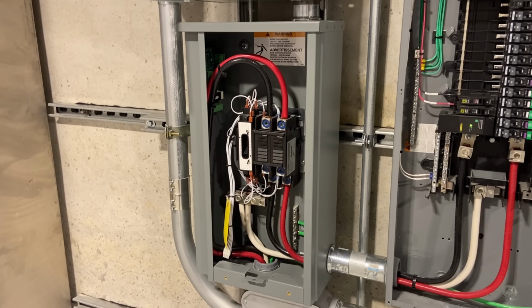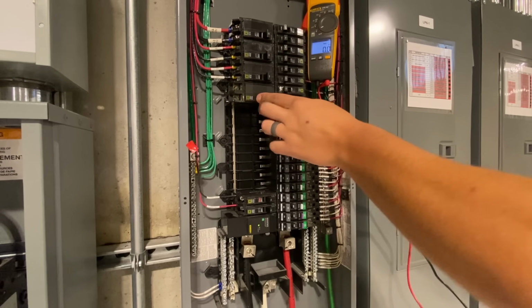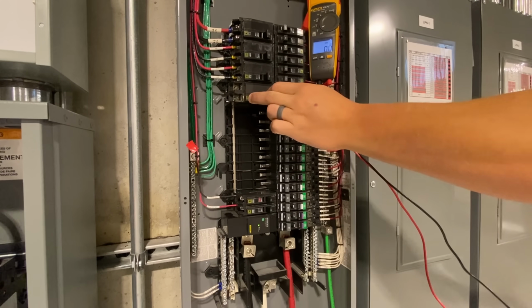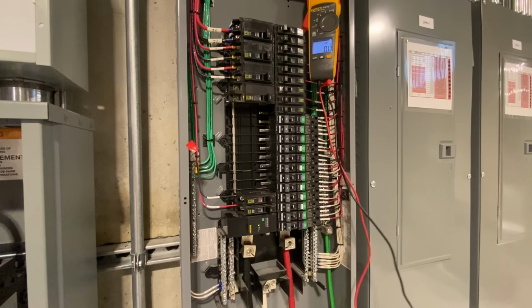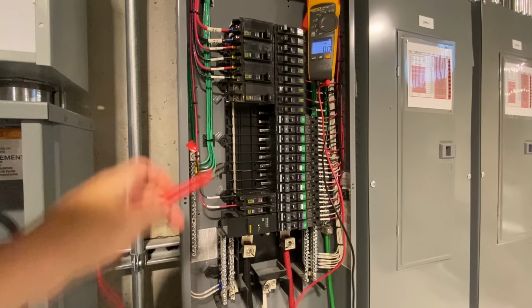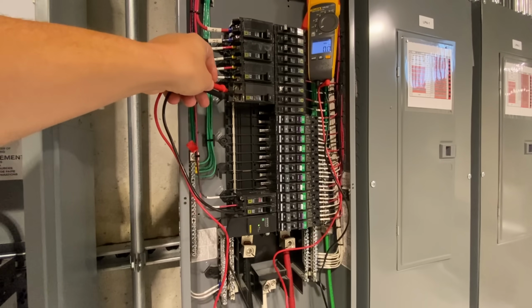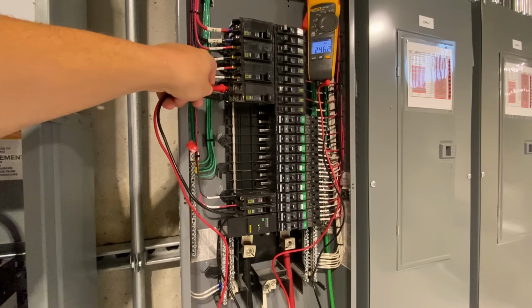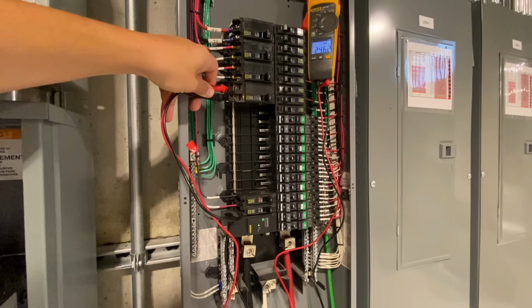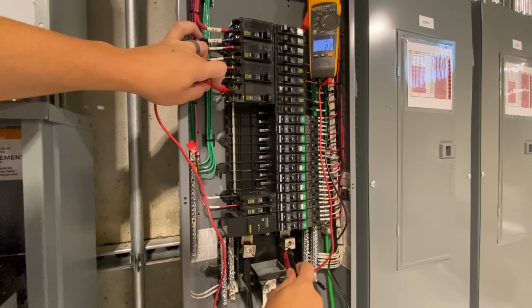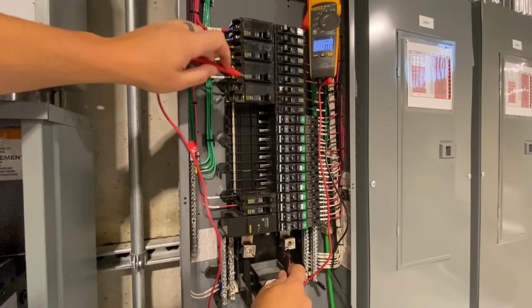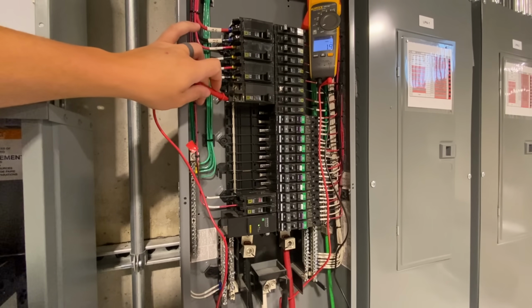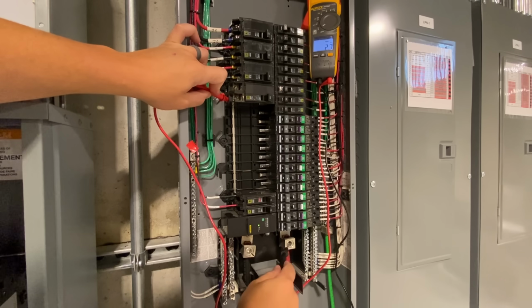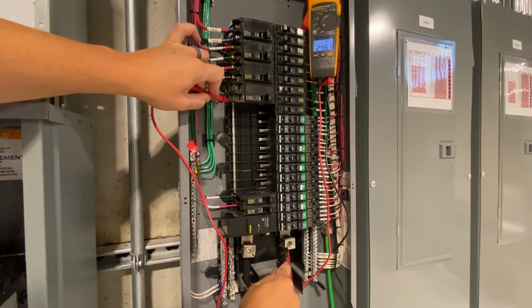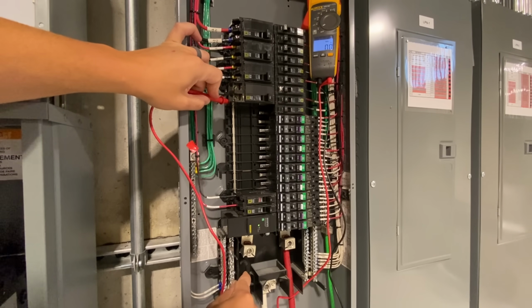Now, one thing I did want to do, which isn't completely necessary, is I want to phase it the same in the I-line panel and at this panel. So the way you want to figure out which phase is which is turn your circuit breaker on first. I got 240. And if I take one lead and go down to the bottom, because that's what I'm comparing it to, you can see I have 0 volts on red. That means that phase is the red phase. If I go down to the other one, I have 240, which means it's the opposite, and that is the black phase. Go to black, I have 0.